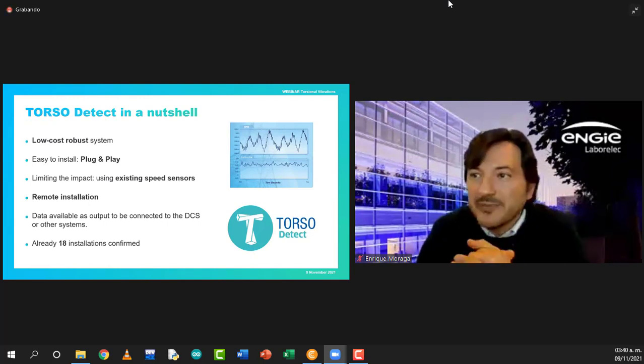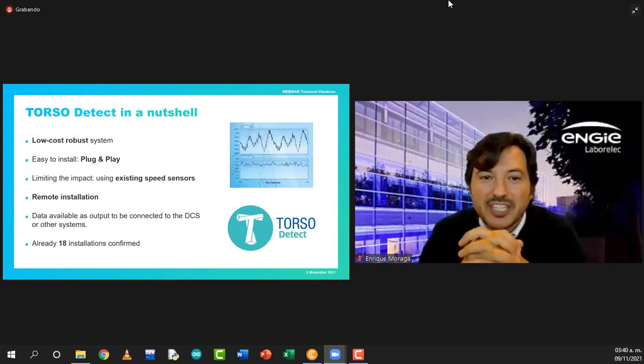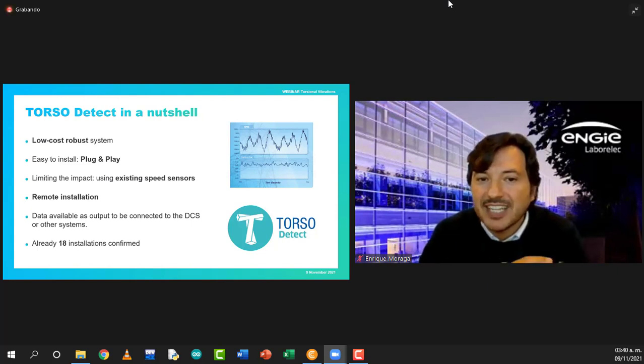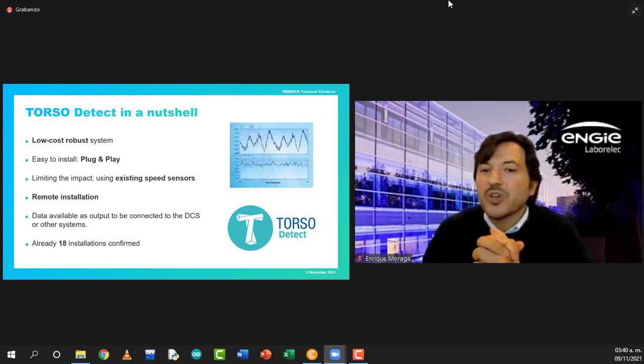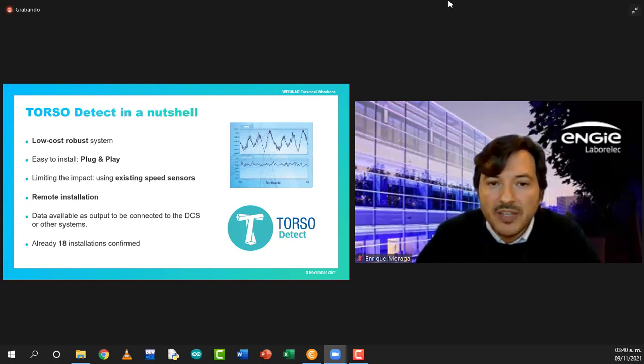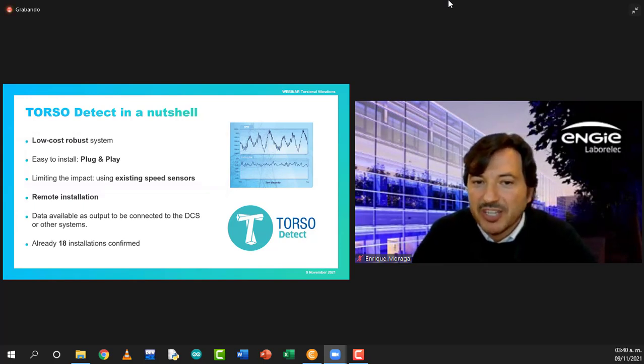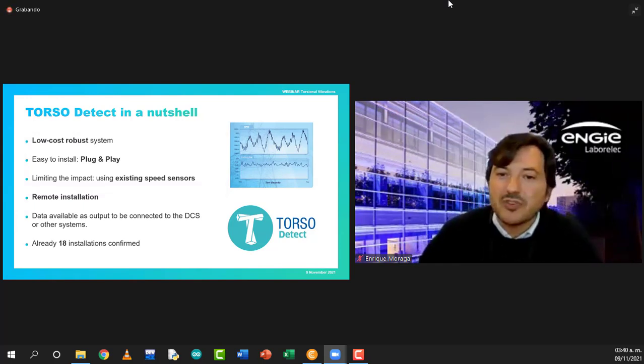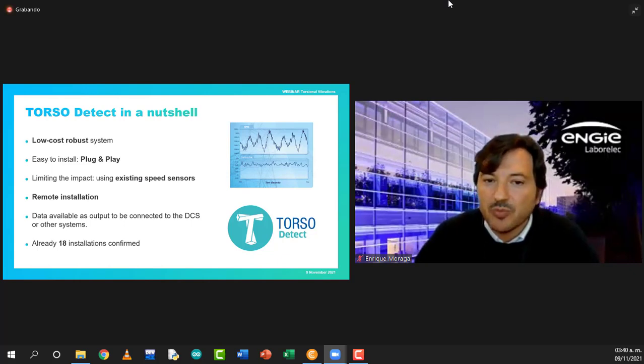So, as a summary, Torso Detect in a nutshell, we could say that it's a low-cost, robust system. It's very simple to install, plug and play, no new sensors are required. The installation can be made by the operator. In fact, we are going to provide an installation procedure and a video to make it possible. The data available in this equipment as an output can be easily integrated into the DCS or even in the lateral vibration monitoring system if there is already one in the power plant. I'm going to say that we are very happy to announce that we have already received the orders for 18 units to install in the next few months.